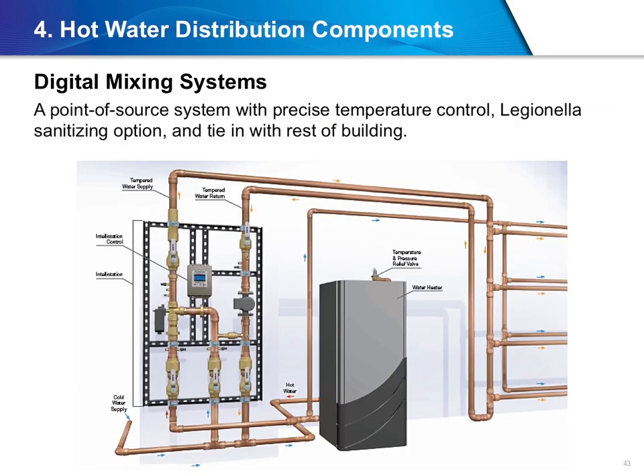As a point-of-source system, a digital mixing station can provide precise control of hot water delivery within 2 degrees of the set point, surpassing industry standards. Further, it eliminates temperature creep within the system, thus eliminating the need for balancing valves. In particular, a sanitization or disinfectant mode can be triggered to briefly raise the temperature above 158 degrees Fahrenheit to induce a rapid kill and purge all Legionella bacteria.